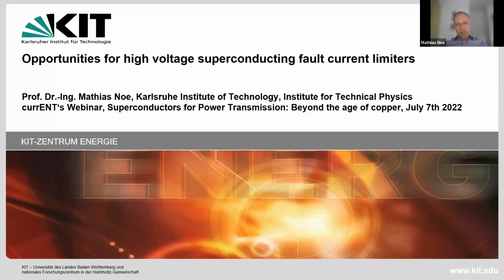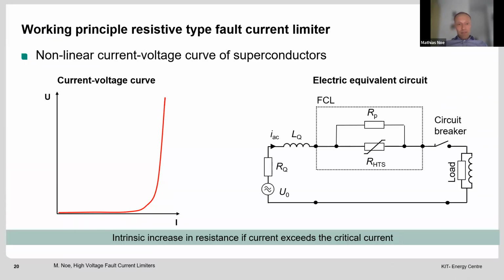Before we continue with the cables, I want to shortly introduce the opportunities for superconducting fault current limiters. I expect some people are not very familiar with that, so I shortly explain what it is. The superconductor has a very nonlinear current voltage curve that you see here on the left side. When you exceed the current, resistance develops, and this is intrinsic just by exceeding the current. And this is what we use in the short circuit that you see here on that side. Here is the superconductor in the middle, and you can put any impedance in parallel to adjust the currents according to the specification.